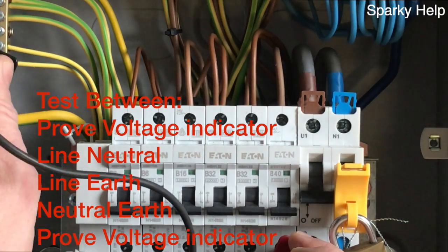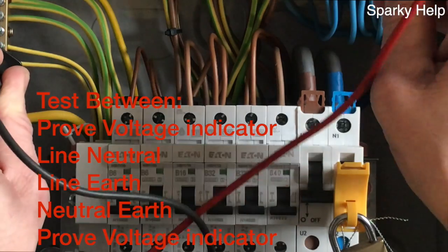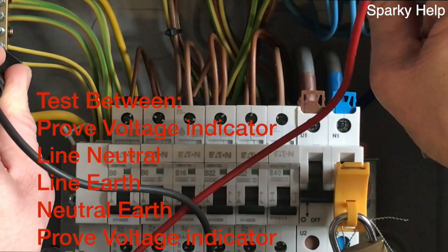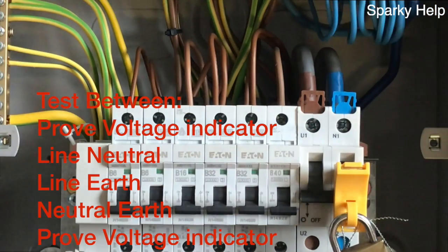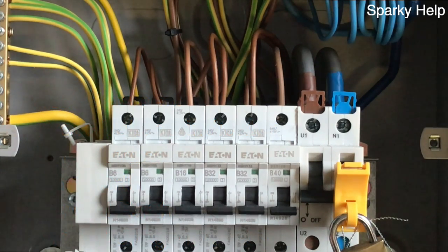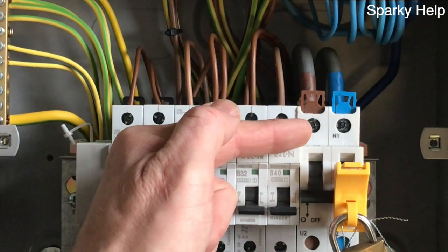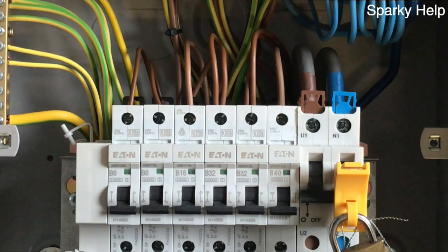line neutral, line earth, neutral earth, and then going to check on my proving unit again. If everything turns up to be 0 volts, apart from obviously on the proving unit, then we now know that this is safely isolated. But remember, the incoming supply up here is still on.